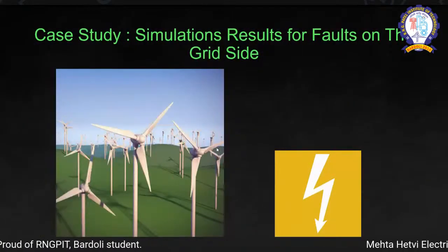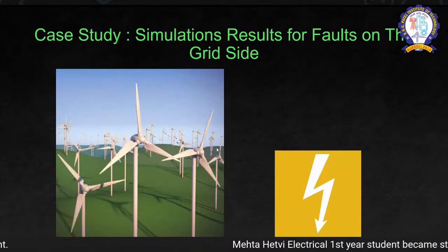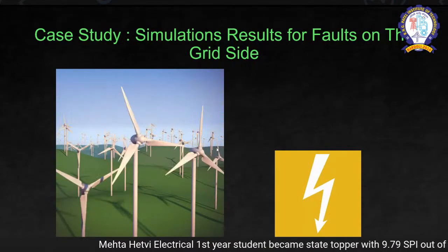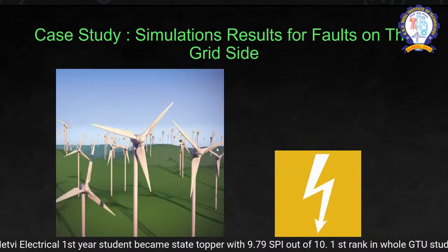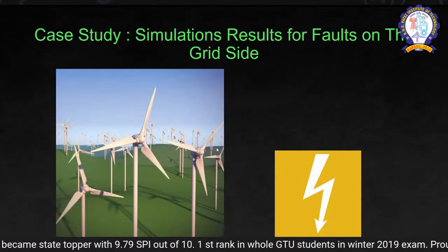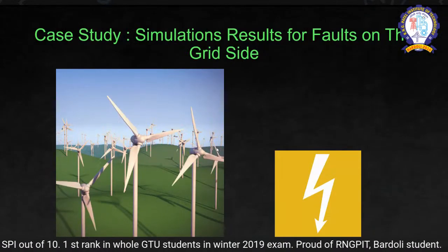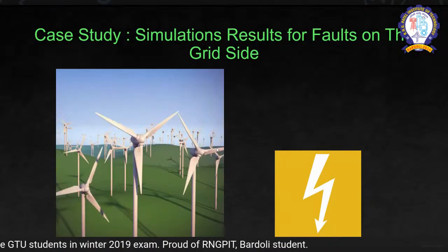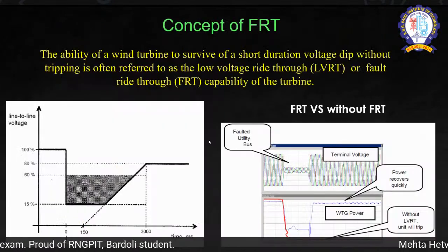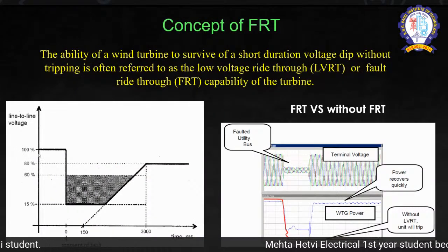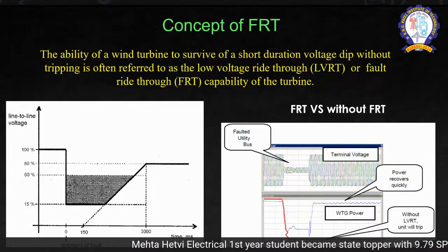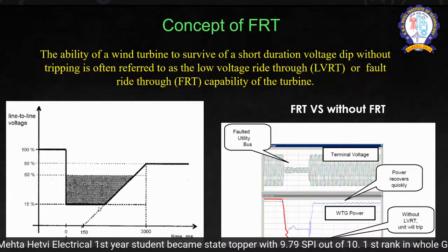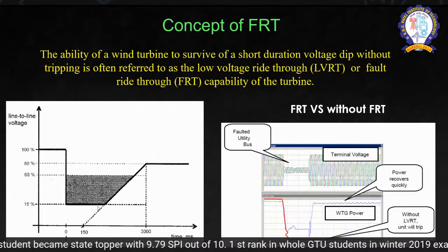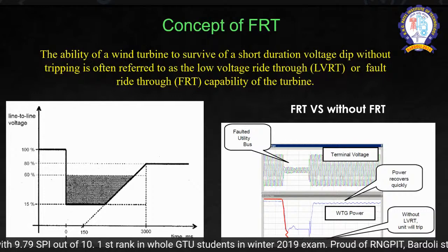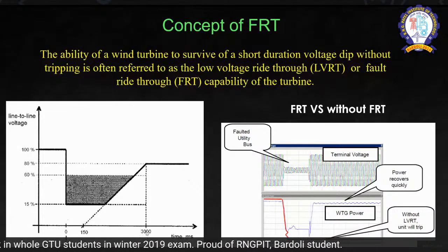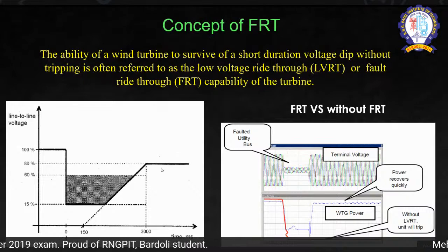Now, when there is a fault in the power system, there is a concept, as I have tried to explain in the earlier part in a very short manner, that is LVRT, low voltage ride through technology. So when there is a fault, the voltage will go down. See, this is the line to line voltage. When there is a fault at this moment, it will go down. Now the power system senses that this is a temporary fault. Then at the end of the momentary fault, within 3000 milliseconds, the 80% voltage has been regained.